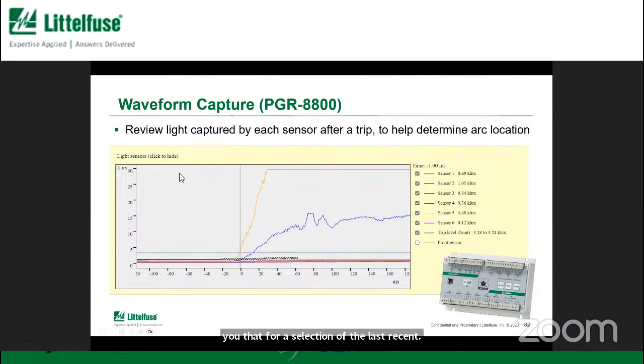So this diagram on the screen, this is some testing I did in our Littelfuse Champaign, which is just south of Chicago. We have a high current laboratory, and we did some arc testing. So this 8800, you could see this green horizontal line was the trip level that was selected, which was 3 Klux. And when we issued the flash, you could see what the light sensor was measuring for light intensity. And this is measured in Klux or kilolux, and that is the measure of light intensity. And that is what the arc flash relays are measuring.